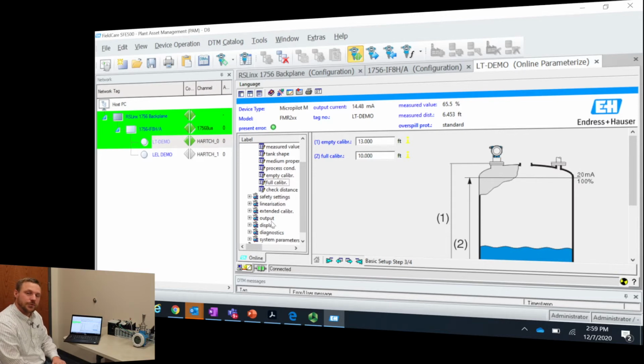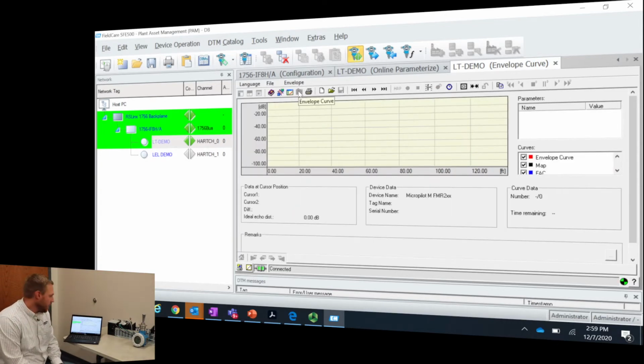We can also troubleshoot the device. That's one of the more valuable benefits of being able to do this: we can perform troubleshooting on a device without actually being on site. Let's say this device is telling the operators that the tank is 100% full, but we know it's only 50% full. We can perform troubleshooting. How we do that is we go into the echo curve profile. This is an option that only radar level transmitters have. It basically pulls in information as to the reflections that the radar is seeing in front of it.